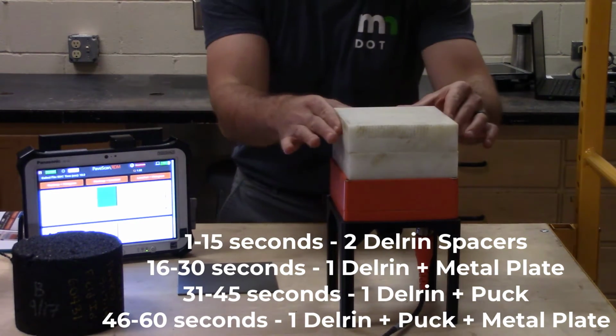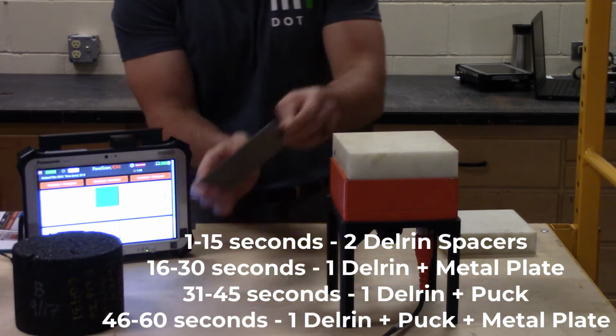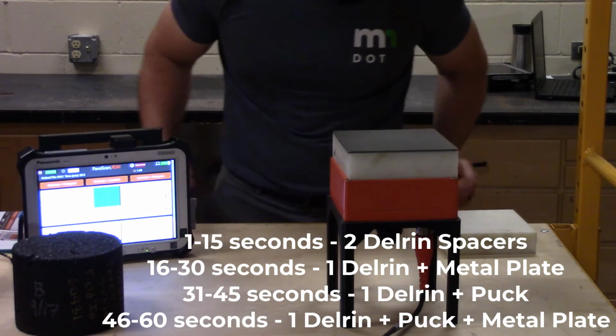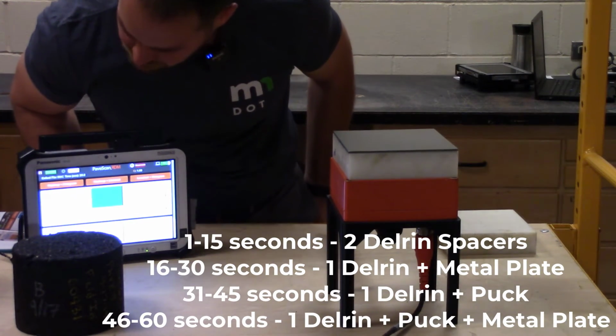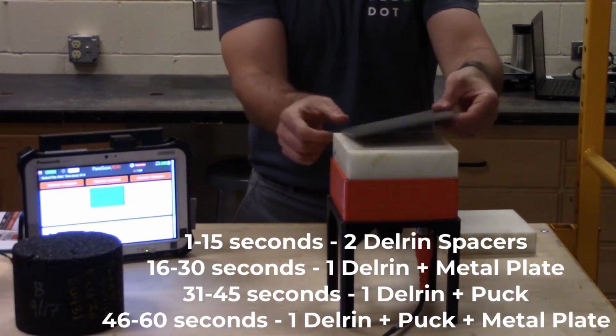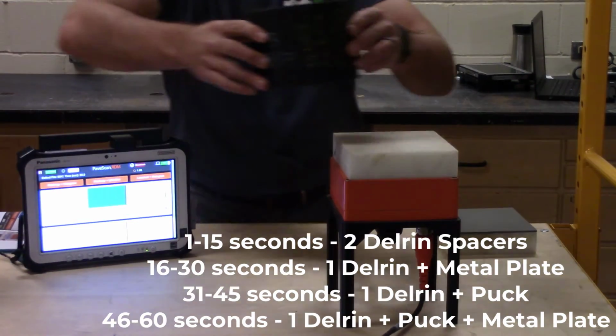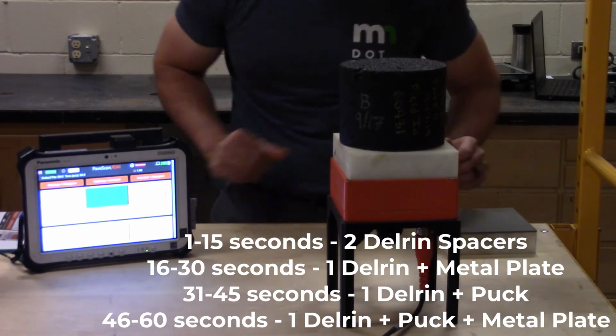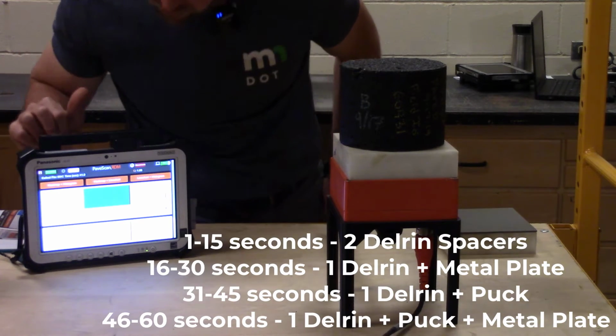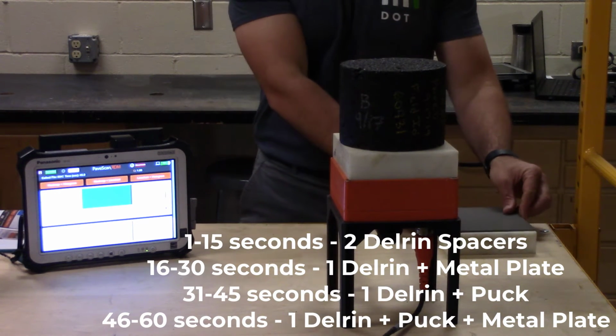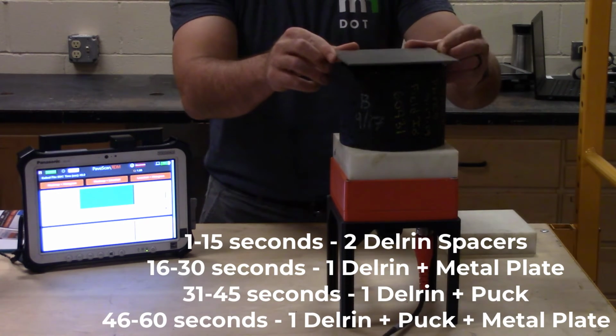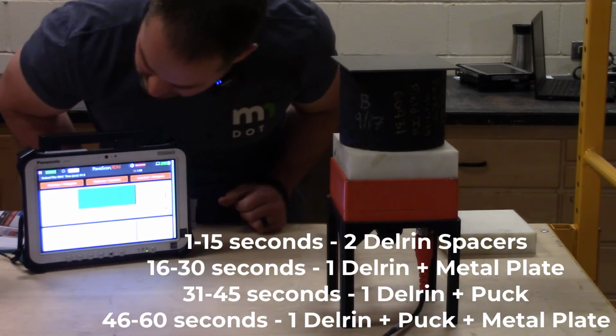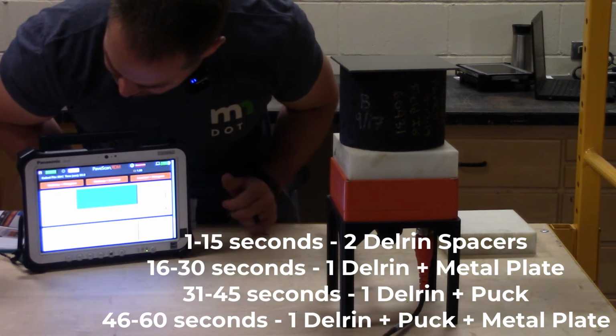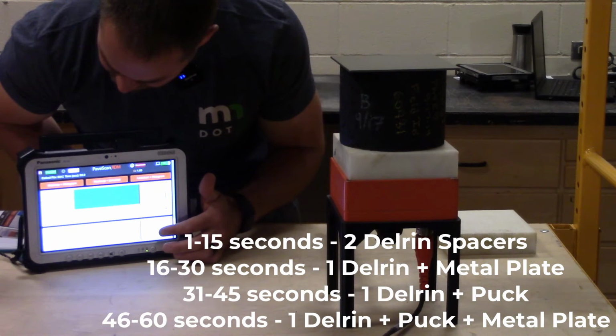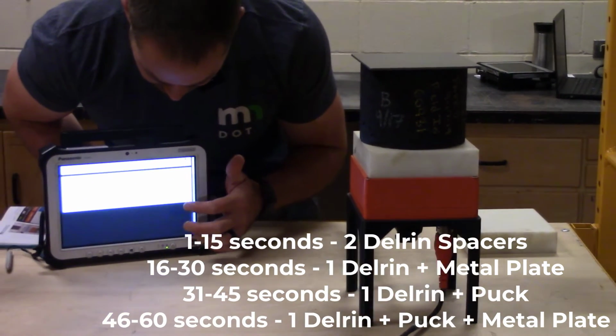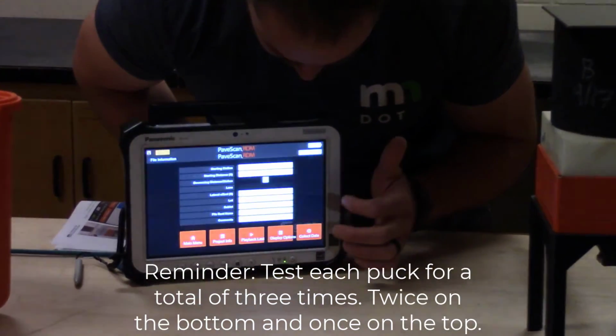So we've hit past 15 seconds, so we're now going to do the metal plate portion. And this is going to collect between 25 and 30 seconds, and then we're able to remove the metal plate and put our puck B sample in place. And this is going to get its measurements between 40 and 45 seconds. And then once that hits 45 seconds, we'll be able to finish our measurement process with the metal plate on top. And that's going to collect between 55 and 60 seconds, and once that hits 60 seconds, we're going to scroll down and press stop and save.